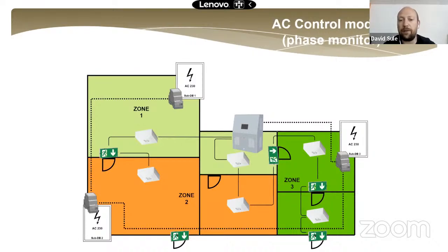We can make separate groups for the lights for zone 1, zone 2, and zone 3, but we can see the DC 24 volt communication and power supply cable is going through different zones. It doesn't matter, because we control the light's address, not the circuit. So when a power failure happens in zone 3, sub DB number 3 will activate the AC control units in zone 3, and the panel will turn on only the programmed group in zone 3.